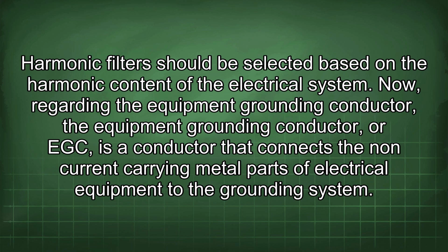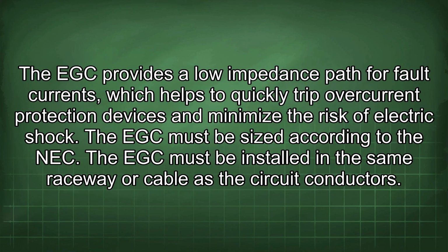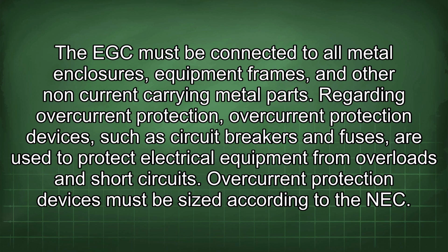Now, regarding the equipment grounding conductor, the equipment grounding conductor, or EGC, is a conductor that connects the non-current carrying metal parts of electrical equipment to the grounding system. The EGC provides a low impedance path for fault currents, which helps to quickly trip overcurrent protection devices and minimize the risk of electric shock. The EGC must be sized according to the NEC. The EGC must be installed in the same raceway or cable as the circuit conductors. The EGC must be connected to all metal enclosures, equipment frames, and other non-current carrying metal parts.